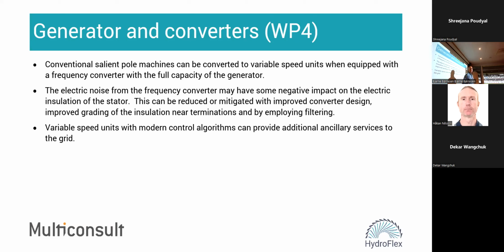to variable speed units when they are equipped with a fully sized frequency converter, and then they design it so that they can manage with sufficient filters or different types of converter topologies to make sure that they can manage the high frequency noise that is generated that can be damaging to the stator windings.